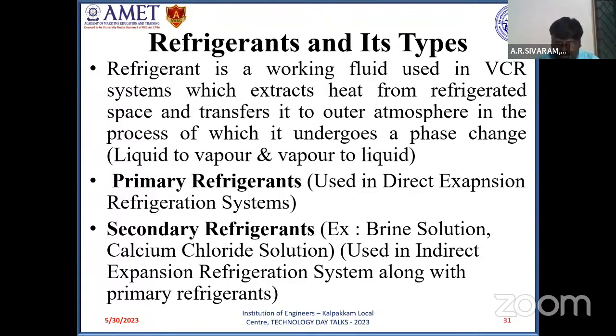That is, the primary refrigerant first cools the secondary, which is a liquid refrigerant. The secondary will then be pumped by means of a pump to the place where heat needs to be removed. So what is the advantage in employing primary and secondary together in an indirect expansion refrigeration system? We can avoid the need for transporting primary refrigerant, because primary refrigerant leakage, of course, is not economical, and moreover, secondary refrigerants are cheaper in nature.